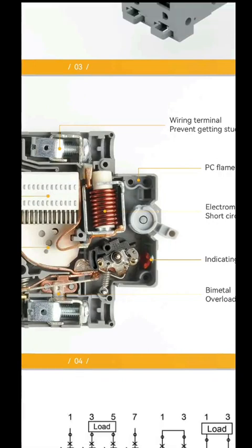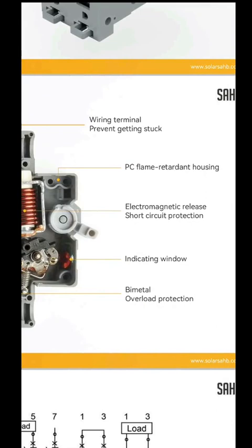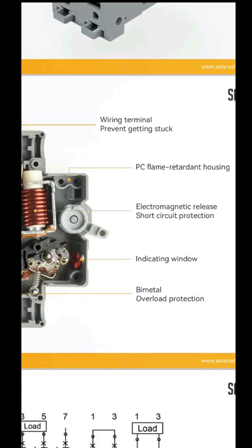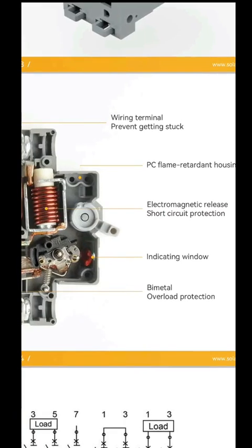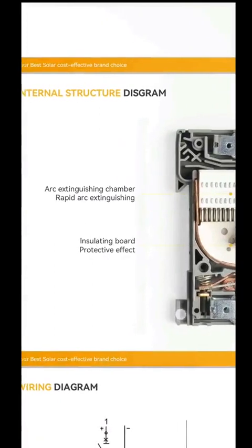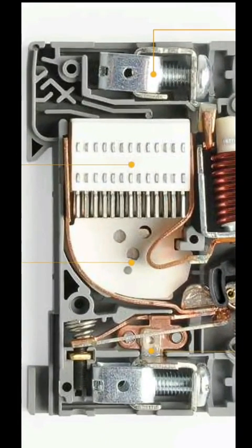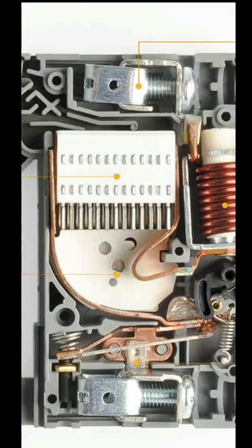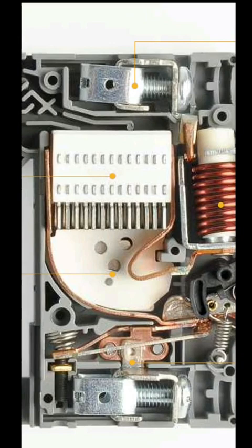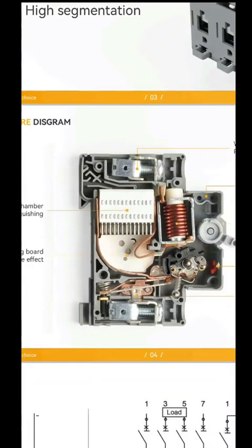You can always look at the construction — it's a good solid stainless steel. The cover is PC flame-retardant. It's got the electromagnetic release for short-circuit protection. It's got an indication window where you can see: if it's red, it's on; if it's green, it's safe. Bi-metal overload protection. And this is the main thing — this is the arcing chamber, the rapid arc extinguisher. The arc will come in and it will extinguish through this chamber, cool it down, and kill the arc. That's why they are different.